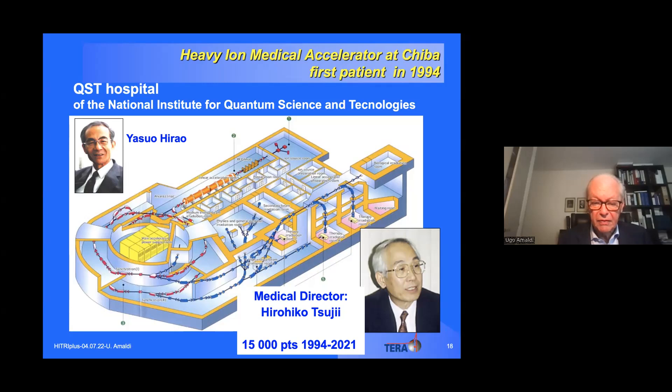When we started — Kraft at GSI and myself at CERN — the basis was indeed Berkeley, but Berkeley had treated patients only with helium. The primary source of clinical information was HIMAC in Japan. Those synchrotrons were originally designed for nuclear physics rather than medical treatment, so they are much larger than necessary — 40 meters radius — which is not required for therapy.